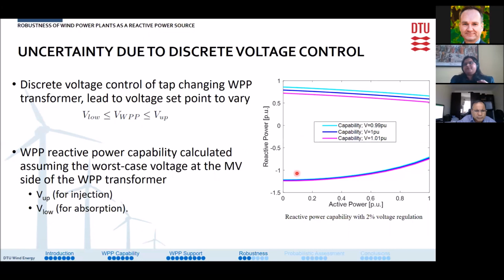Now, if we draw the reactive power capability as shown in the figure here, for these three voltages, then we see that the reactive power capability due to the higher voltage is the most restricted one. Well, this is the case in case of reactive power injection. If it's reactive power absorption, it will be reverse or opposite. Anyways, in order to have a conservative approach to deal with the uncertainty due to this discrete voltage control action, what we do is we proceed with the worst case, the most restricted reactive power capability of the wind power plant, and do further studies.